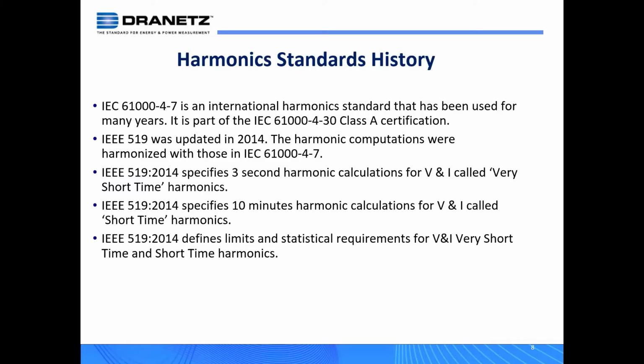Well, the IEEE in 2014 updated the IEEE 519 recommended practice on harmonics. And the harmonic computations were harmonized, or in other words, made the same as those in the IEC 61000-4-7. So what that meant for Dranetz is that, well, we've been measuring to this standard for many, many years, probably 10 years or so at that point in 2014. But the IEEE didn't stop there. They also added a couple of customized parameters just for the IEEE version of the standard.